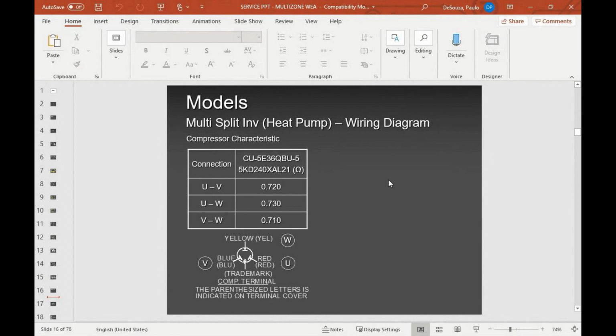In our service manual, you will see a page that shows you the value of each and every thermistor. Okay, I will tell you, based on my field practical experience, I have yet to see a defective sensor, meaning it got weak and died off. Not that it won't happen. At some point it will get defective, maybe 10, 12, 15 years to come. But in my 6 years with Panasonic, I have yet to see a defective sensor. The only defective sensor that I've seen was cut. How it got cut, I really don't know. But if it cuts, obviously you will get a short, and when you get a short, you get an error code, H15, H16, whatever.